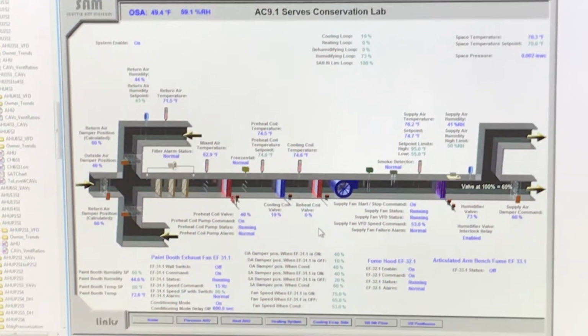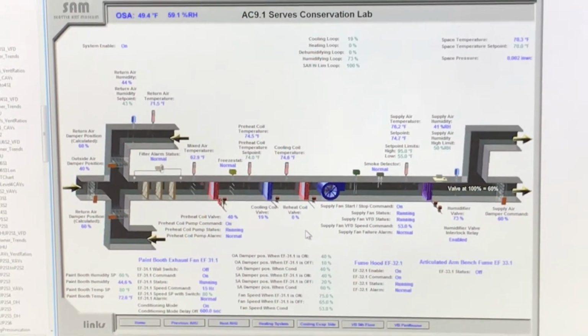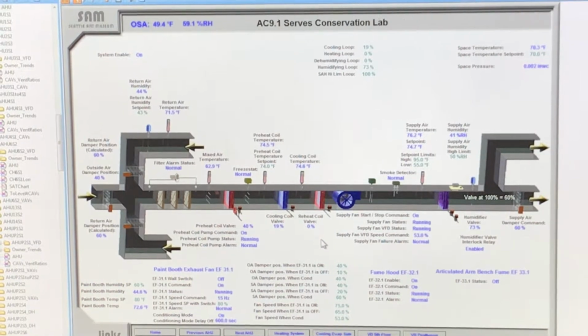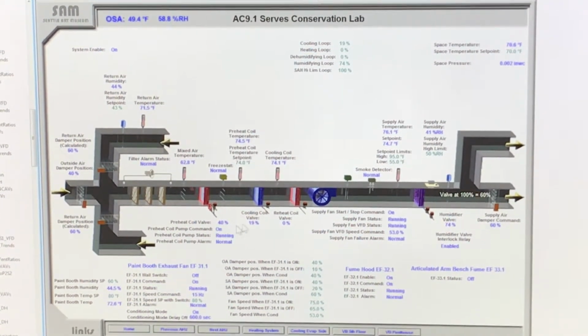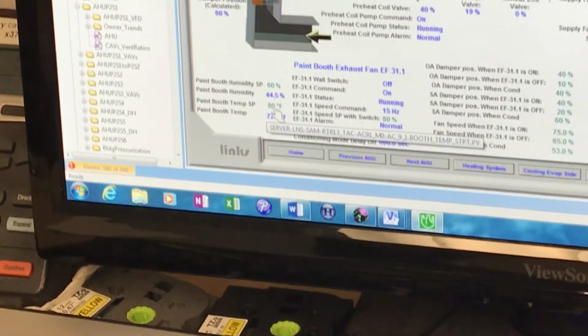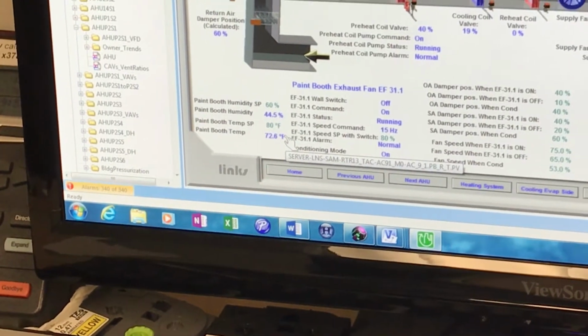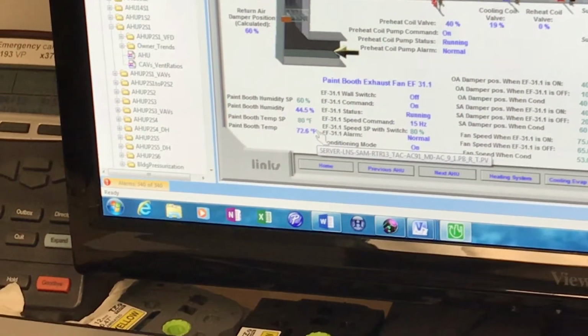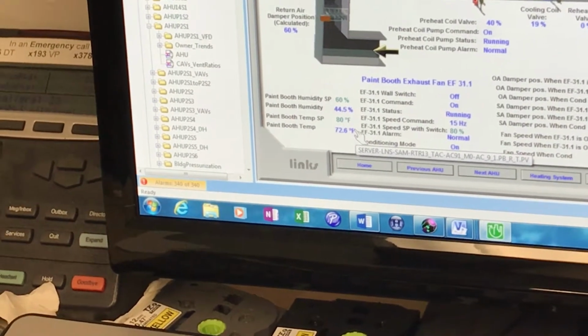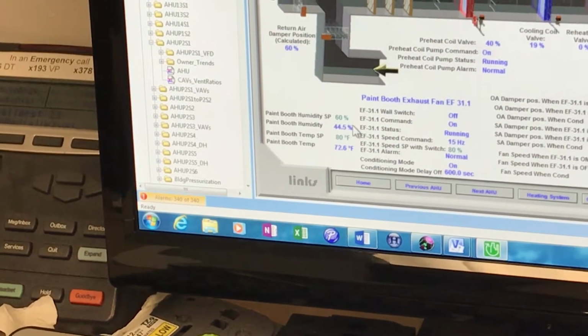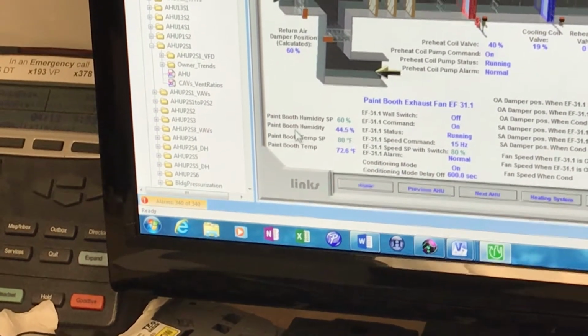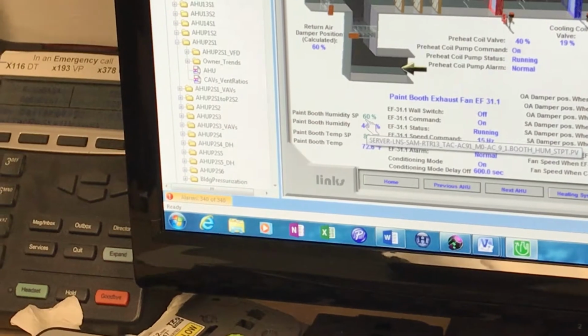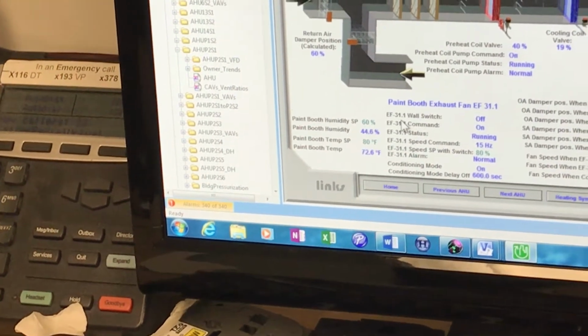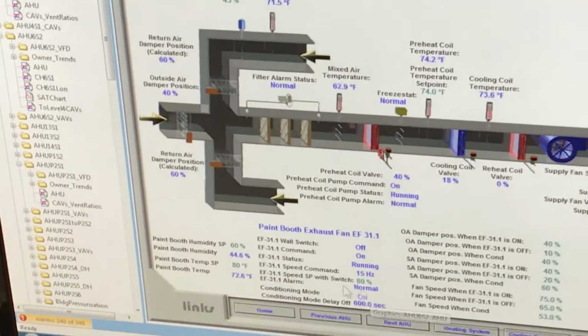Alright, AC 9.1. This is probably the last of the little bit that we have. 9.1 serves the conservation lab, and they added a little control here for paint booth humidity and temperature, so that the paint booth fan would come on to control the humidity and temperature now. So these set points here are what control it. Whenever the booth humidity gets above 60%, it's going to turn on exhaust fan 31.1. Okay. Yes, yeah.